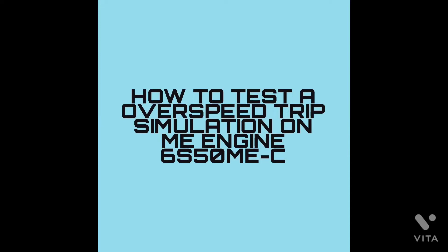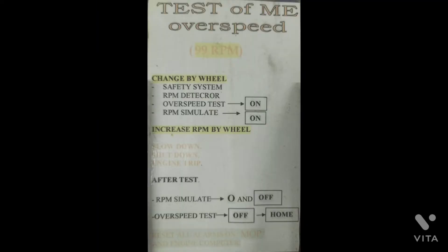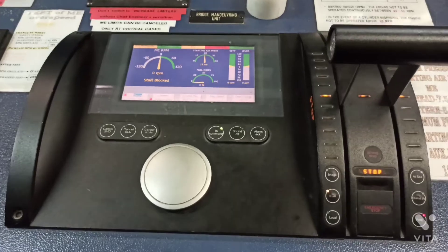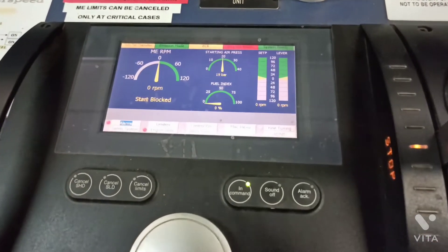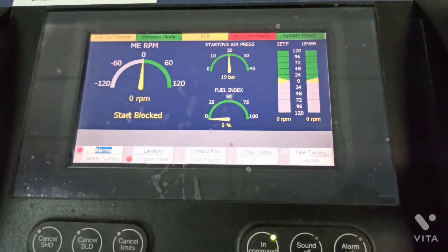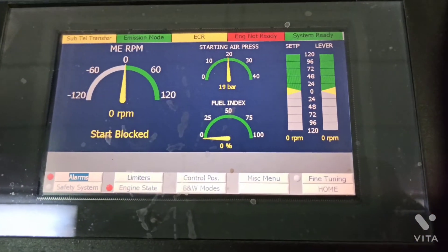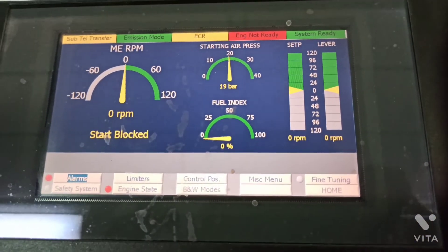Hi guys, welcome to my YouTube channel. Today we are going to see how to simulate an over speed test. First of all, you need to go to the main engine telegraph panel.